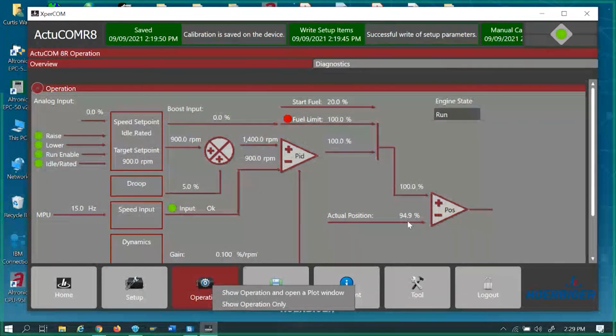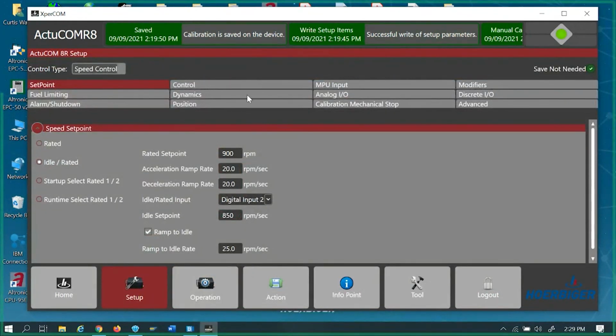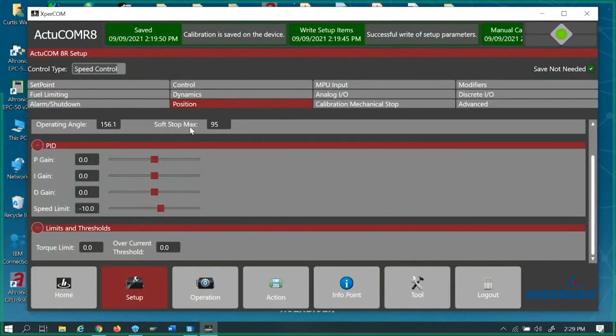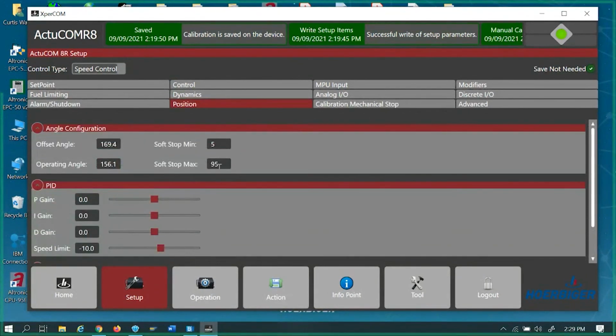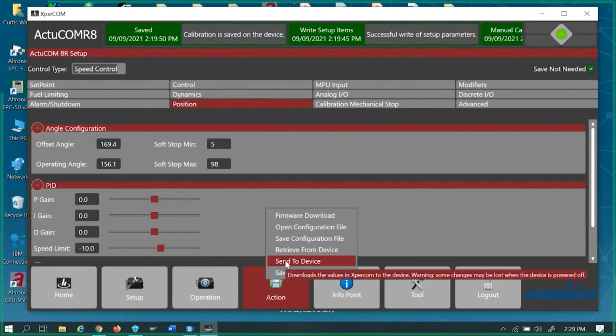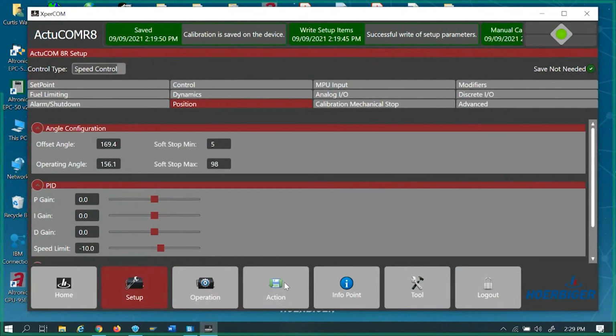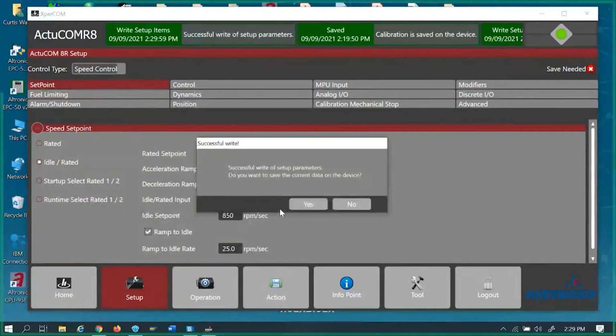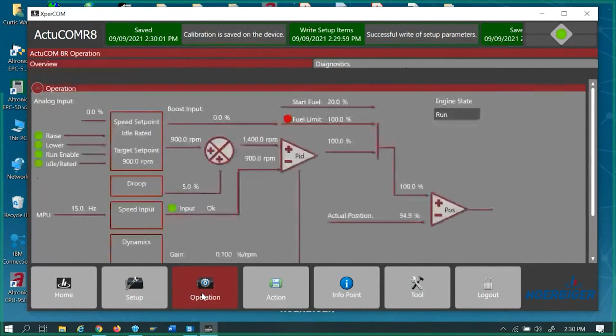I'm not there. My governor is basically all the way open. Why am I only at 94, say 95% open? I'm only at 94% open because I told it on this position that I got a soft stop at the top end at 95. So if I went to 98, say I didn't have any fuel, and I send it to that device, go back to my operation. Now this thing jumped up to 98. It gave me a little bit more fuel.